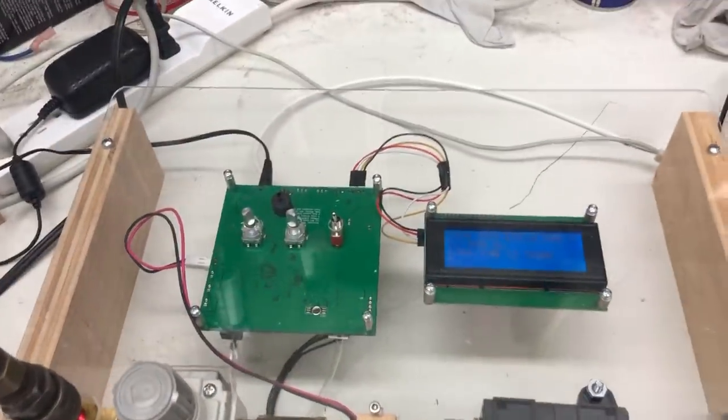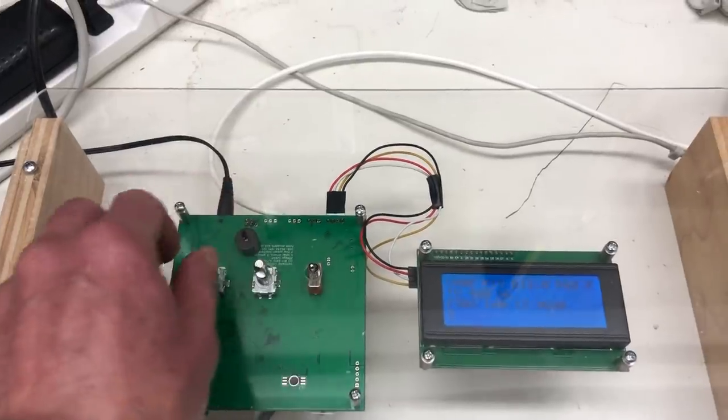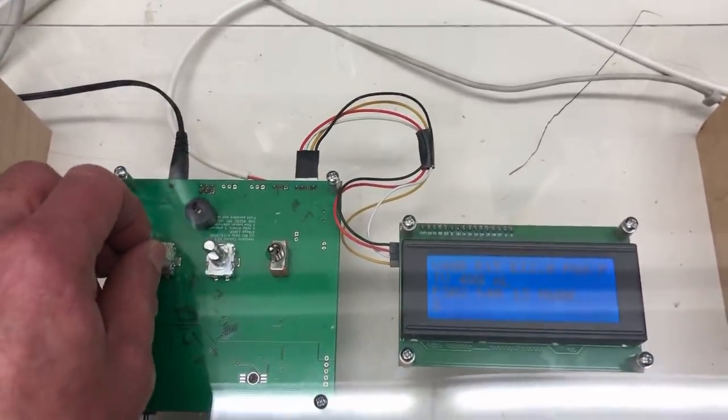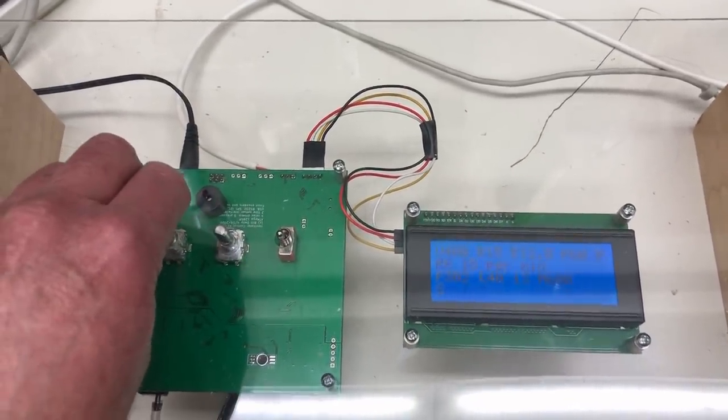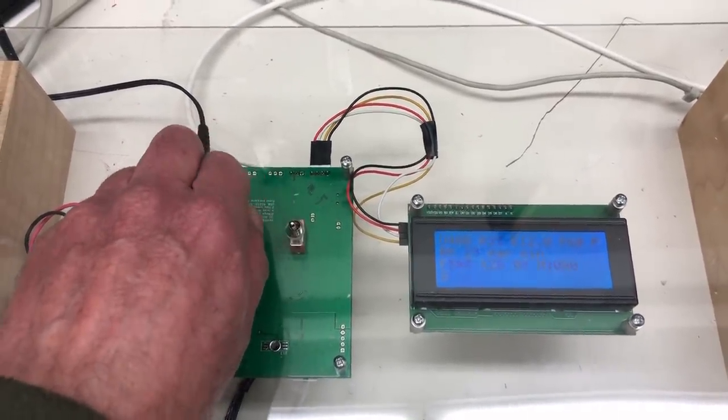The unit operates with a simple two-encoder interface. The left encoder selects a parameter. So here it's on tidal volume. If I turn the encoder, I can change respiratory rate. And in each parameter, the right encoder changes the value of that parameter.